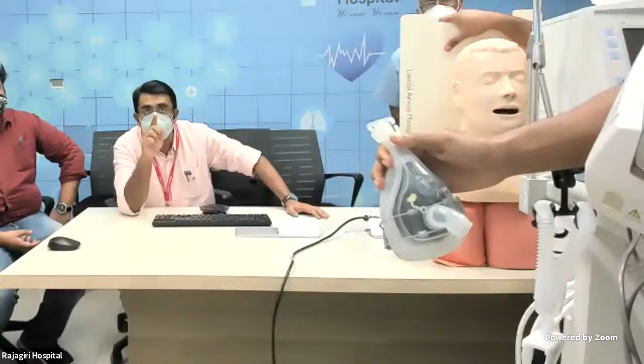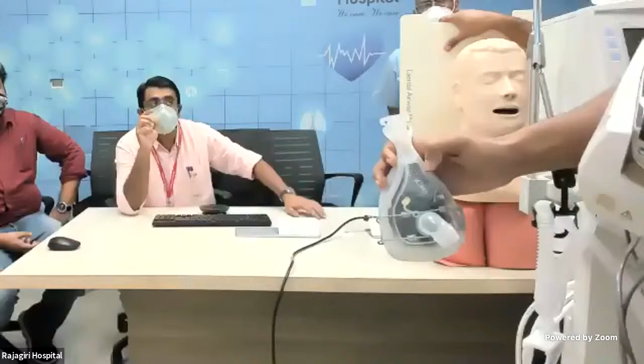You can see over here there should be an inspiration and an expiration. The connector wire gives the inspiratory flow, but the expiration happens through the mask, which is vented. There is an opening there. Whereas the NIV mask connected to the ventilator is not vented, the smaller machine is vented. Through the vent, the aerosol comes out from the patient, which can be infectious. That is why the smaller machines are not advisable in a pandemic situation, because of the risk of healthcare infections.